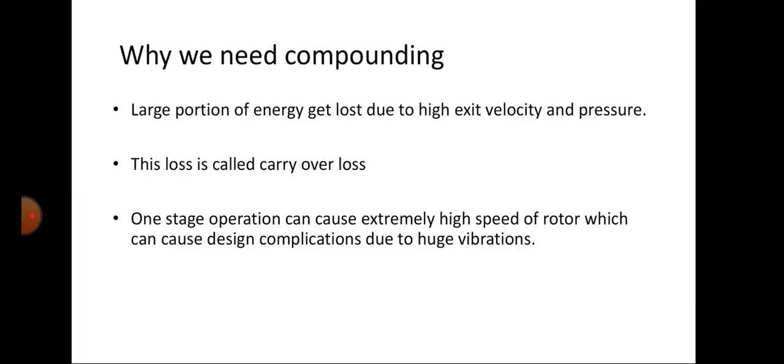So why do we need to do compounding in the turbine? In a single-stage normal turbine, the exit velocity and pressure are very high at the exit, which means an energy loss occurs at the exit. In order to overcome this energy loss, we need to compound the turbine. This loss is referred to as carryover loss — when pressure and velocity leave without being utilized, it is a loss. So in order to compensate for that, compounding is done in the turbine.